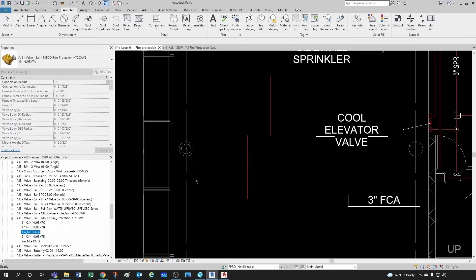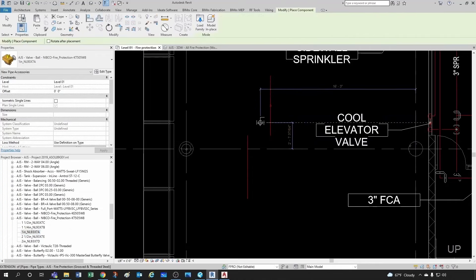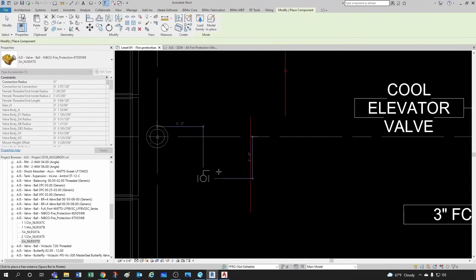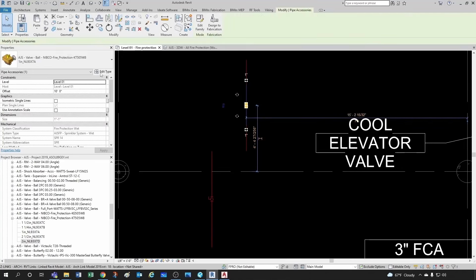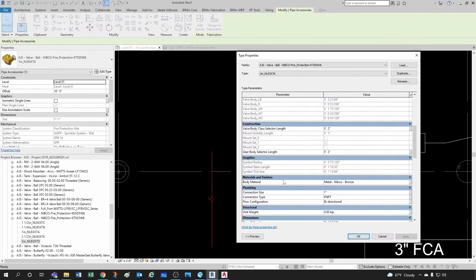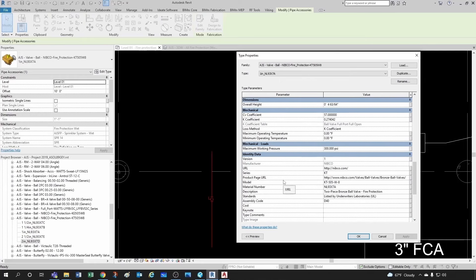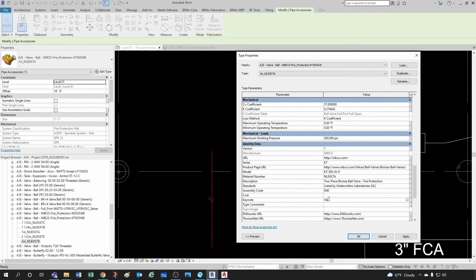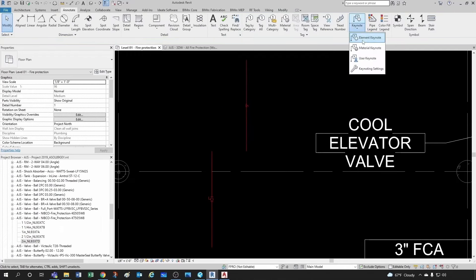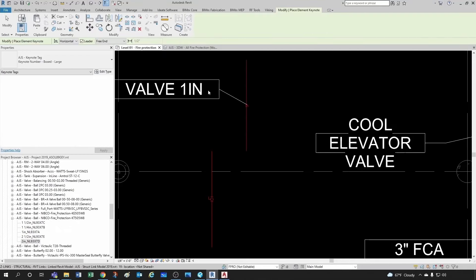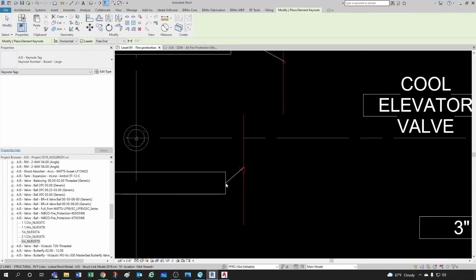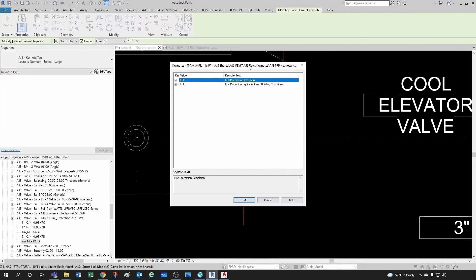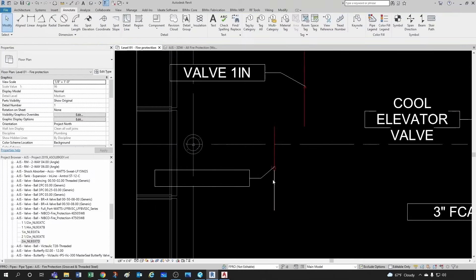Let's use this one-inch and this two-inch valve. What I want to see is how this behaves. If I come here and do Edit Type and go down to keynotes, I'll say 'valve one inch.' Now if I try to use my keynote, for this valve I have 'valve one inch.' But if I try to do the same for the two-inch, it's popping my keynote file because I have nothing on this particular type.